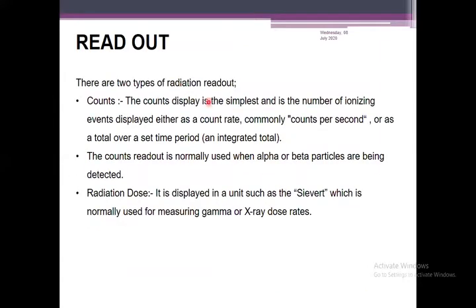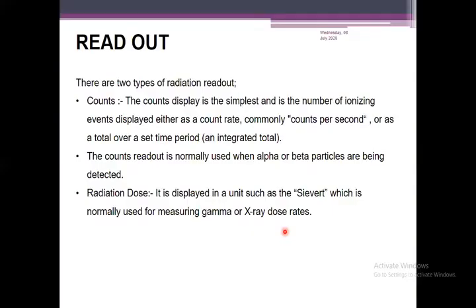There are two types of readout. The first is radiation count readout — the simplest type — displaying the number of ionizing events either as a count rate, commonly counts per second, or as a total over a set time period. Count readout is normally used when alpha or beta particles are being detected. The second is radiation dose, displayed in units such as the Sievert, which is normally used for measuring gamma or X-ray dose. These are the key features of the Geiger-Müller counter covered in this section.